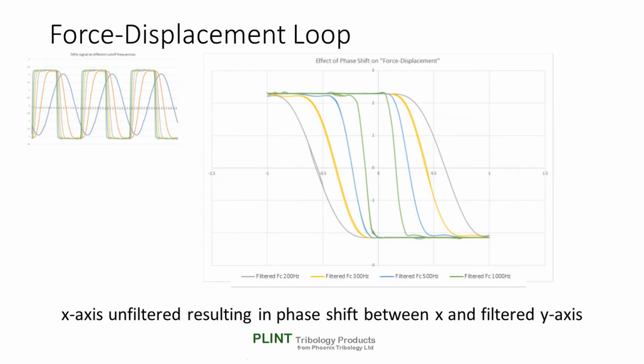We normally apply some filtering on all measuring channels in order to eliminate high frequency signal noise and aliasing. The same characteristic filter should be used on all channels, especially in high frequency systems, to ensure that the information from different channels can be directly correlated and is not subject to differing time delays.